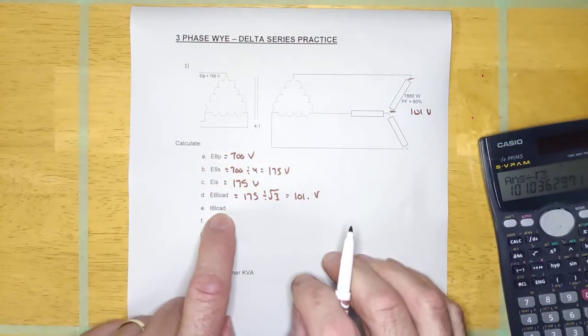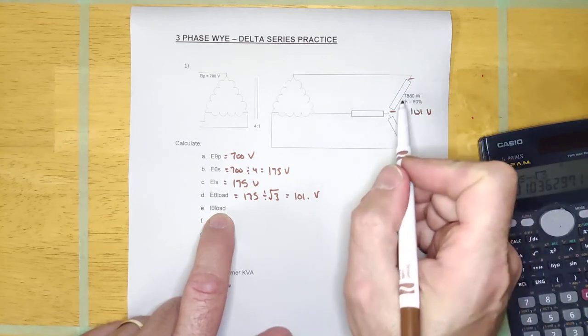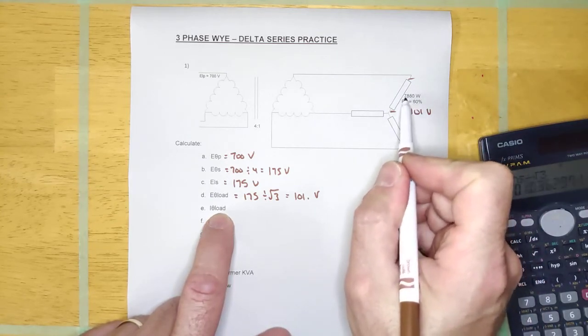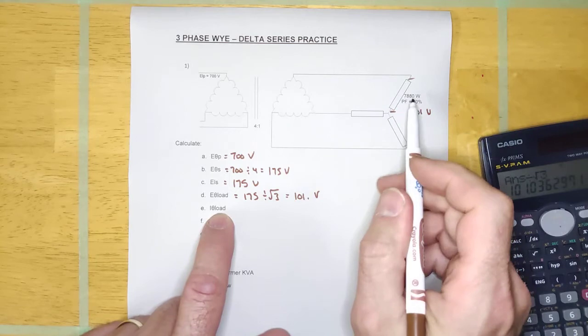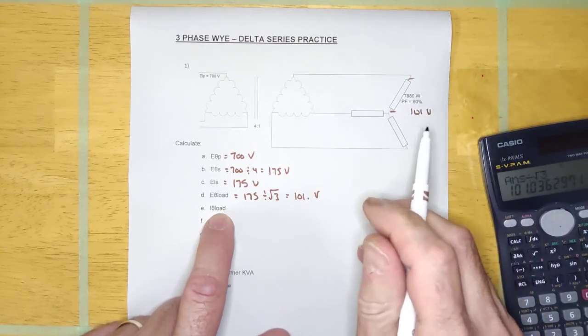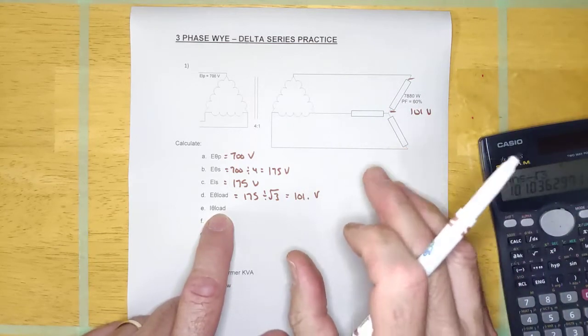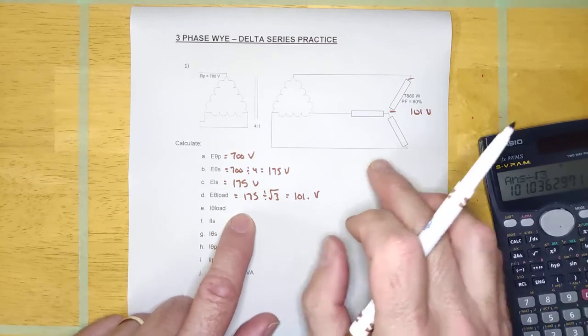Now we have to calculate I-phase load. Again it's a mystery load. It does have a power factor. It says it's 7880 watts. Now you've got to be careful here because the current is not going to be the watts divided by the voltage, okay?